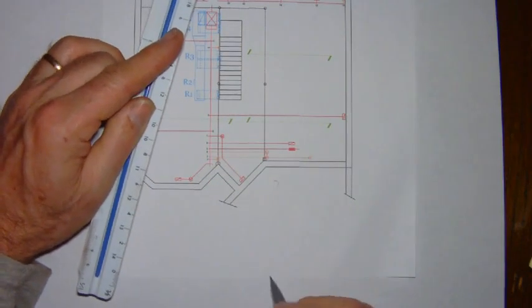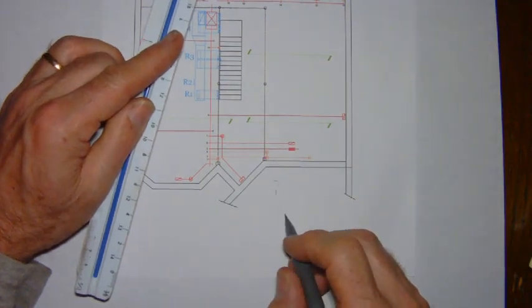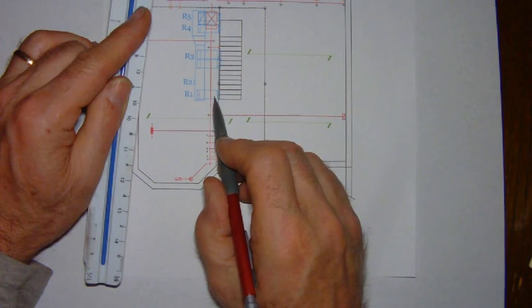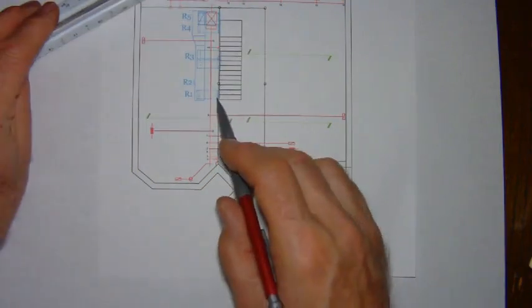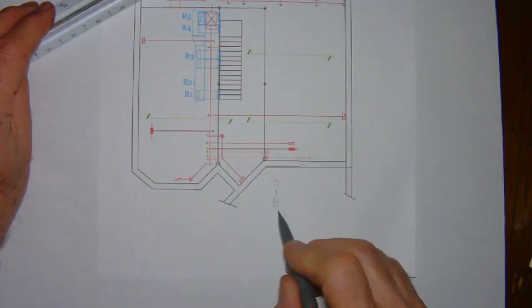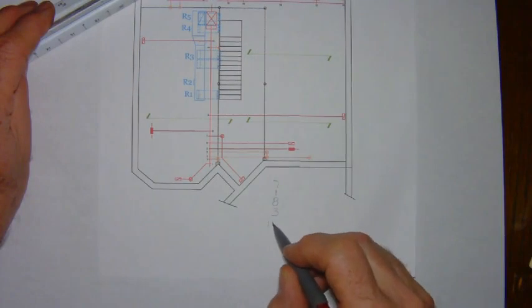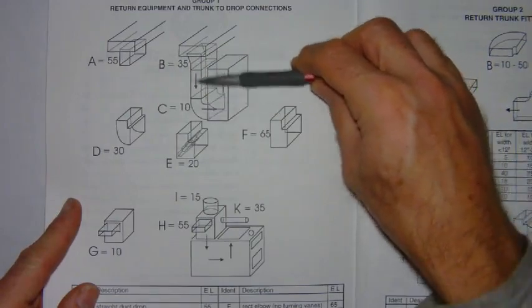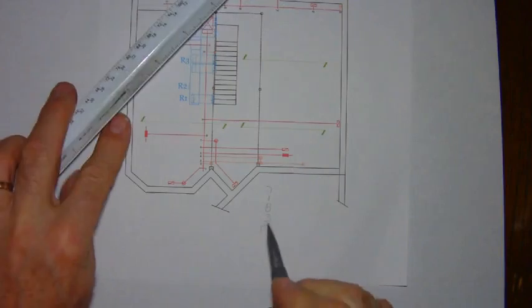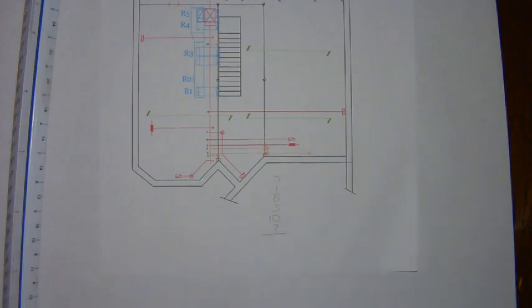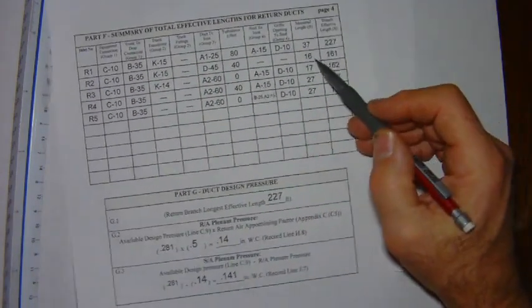we've got seven feet on the second floor. We've got one foot through the first floor header. We've got eight feet through the first floor. And now we've got three feet running horizontal from the plate opening over to the duct. Now we've got 10 feet going over to our drop. And because the basement is seven feet tall and our drop essentially extends from the ceiling all the way down, we would add seven feet.